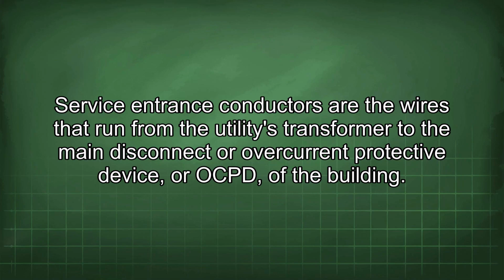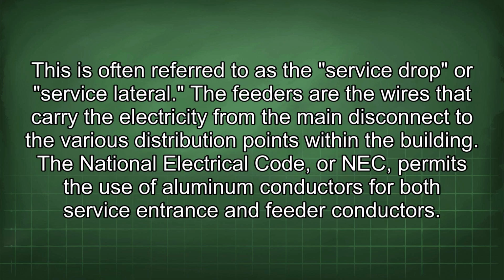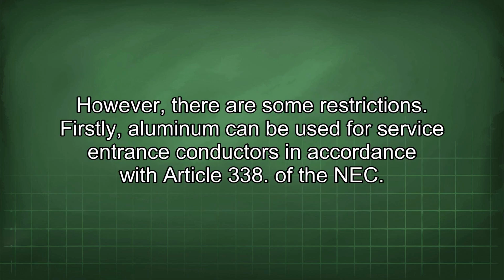Service entrance conductors are the wires that run from the utilities transformer to the main disconnect or overcurrent protective device, or OCPD, of the building. This is often referred to as the service drop or service lateral. The feeders are the wires that carry the electricity from the main disconnect to the various distribution points within the building. The National Electrical Code, or NEC, permits the use of aluminum conductors for both service entrance and feeder conductors. However, there are some restrictions.